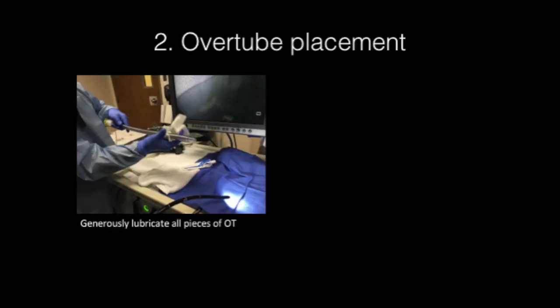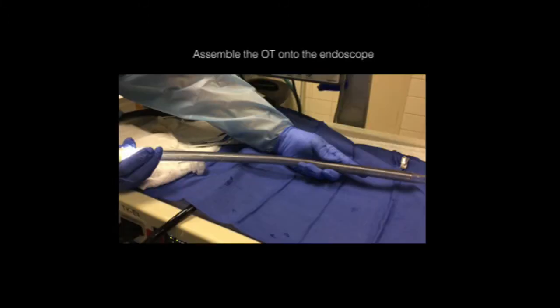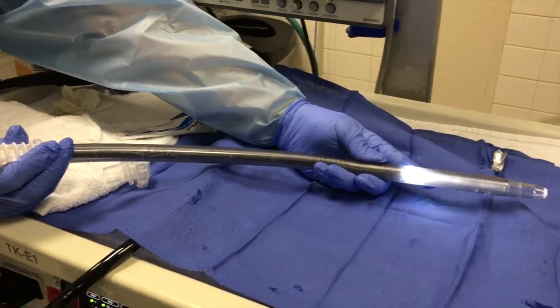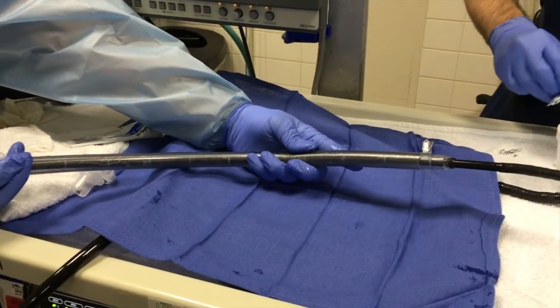For the correct use of the overtube, we should follow several steps. A: Generously lubricate all pieces of the overtube with gel and water — if you use only water, this might not be enough. B: Load and lock the inner tube inside the outer tube. C: Assemble the overtube onto the endoscope, ensuring that the tip of the endoscope advances beyond the tip of the overtube.